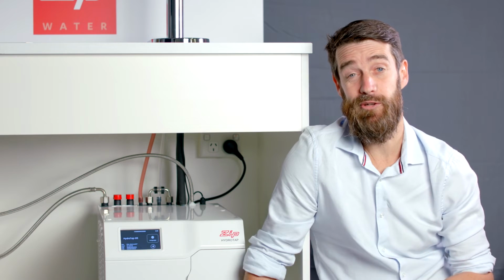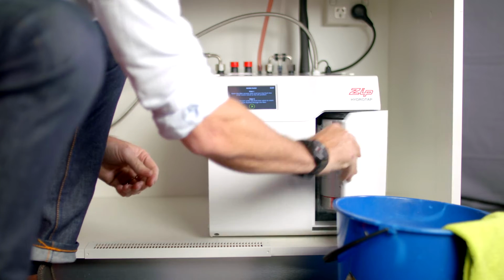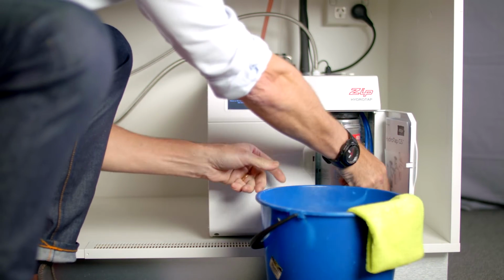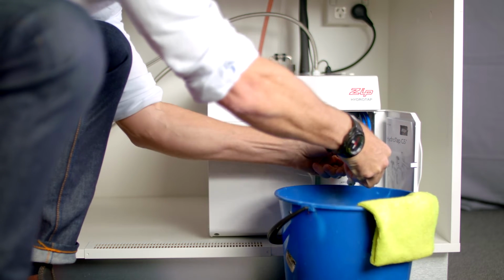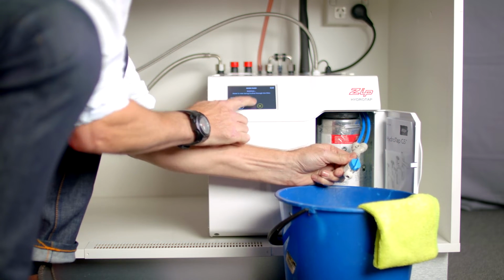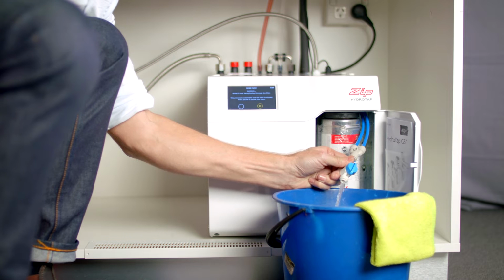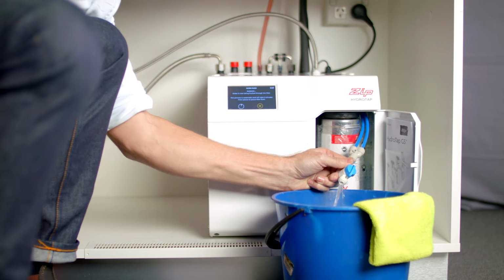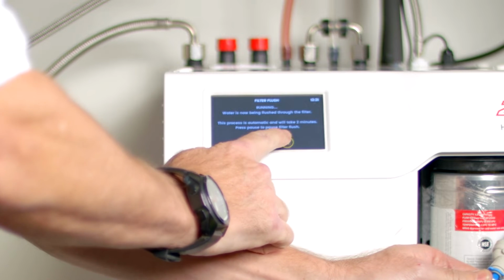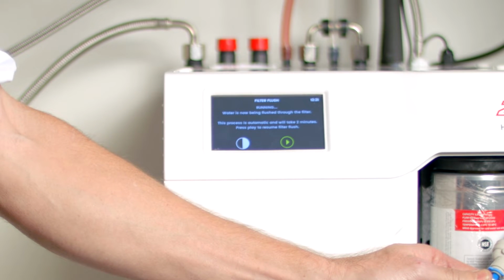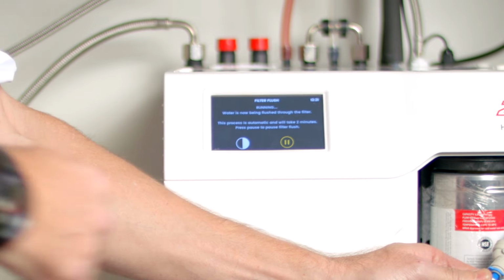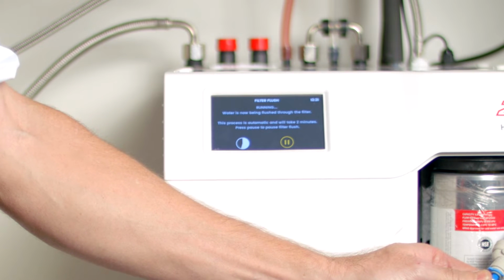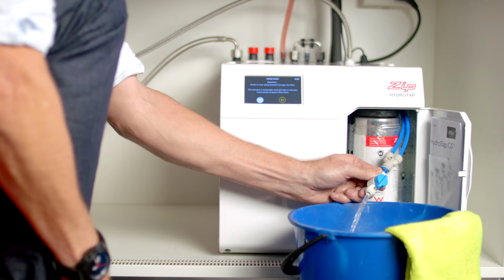Next, the internal filter needs to be flushed. Using a bucket, place the filter flush hose in the bucket and open the stopcock. Press the play button and the filter flush process will start. This process is timed to take 2 minutes. If you need to pause the filter flush, press the pause button on the LCD. When you're ready to resume the filter flush, press the play button. Once the filter flush has stopped, turn the stopcock off and give it a shake.